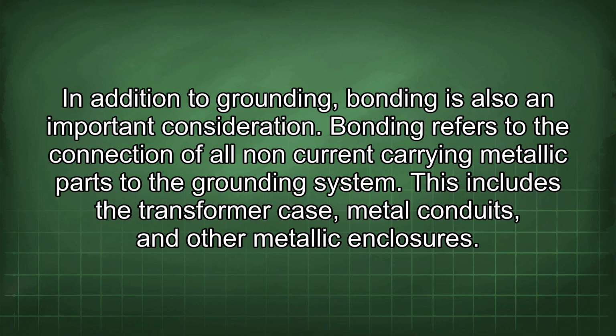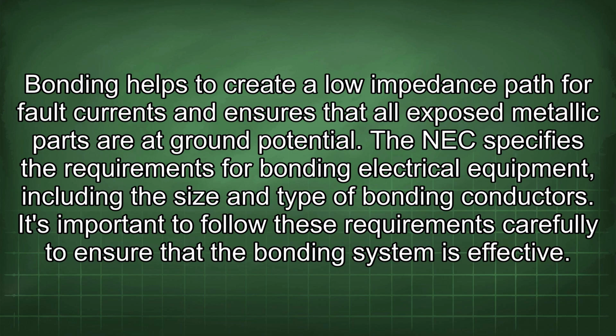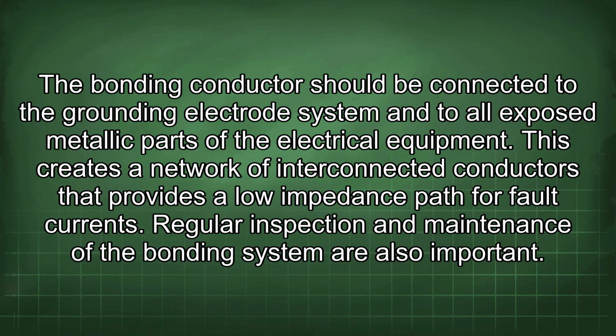In addition to grounding, bonding is also an important consideration. Bonding refers to the connection of all non-current carrying metallic parts to the grounding system. This includes the transformer case, metal conduits, and other metallic enclosures. Bonding helps to create a low impedance path for fault currents and ensures that all exposed metallic parts are at ground potential. The NEC specifies the requirements for bonding electrical equipment, including the size and type of bonding conductors. It's important to follow these requirements carefully to ensure that the bonding system is effective. The bonding conductor should be connected to the grounding electrode system and to all exposed metallic parts of the electrical equipment. This creates a network of interconnected conductors that provides a low impedance path for fault currents.